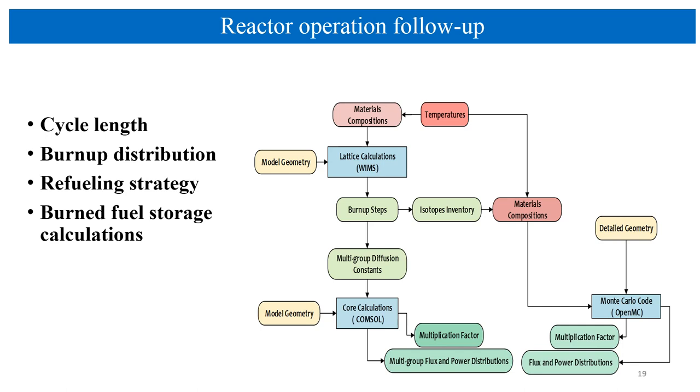Here also, if I have a burned fuel, after removing the fuel assembly from the core and moving it to a storage or fuel storage tank, I have to prevent criticality in the storage tank. So I have to allocate certain positions for the fuel elements, maybe separated by water or something, but it shouldn't achieve criticality. But also I have to calculate using another calculation to prove that this configuration for the fuel storage tanks doesn't reach criticality. I can do this using deterministic and Monte Carlo calculation. In both cases, the main difference is the time.